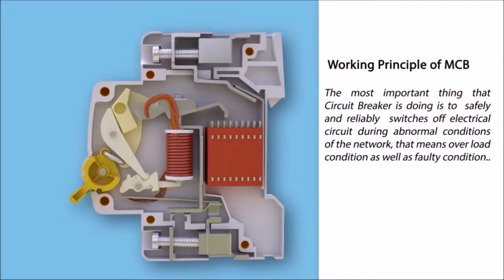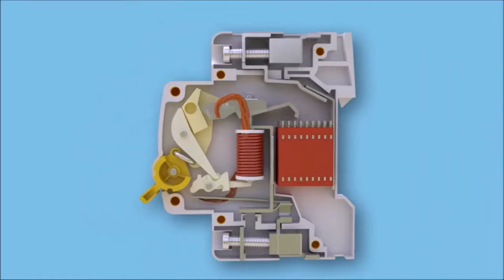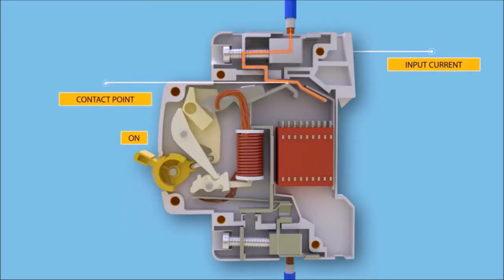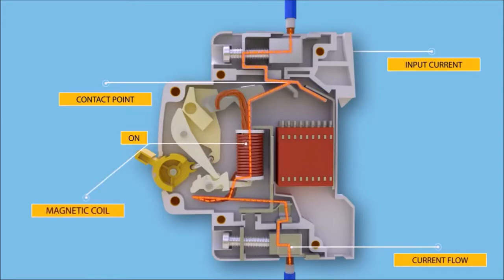Working principle of circuit breaker. The most important thing that a circuit breaker does is to safely and reliably switch off an electrical circuit during abnormal conditions of the network, that means overload condition as well as faulty condition. Under normal working conditions, the circuit breaker works when we switch the operator manually from position off to position on. Electric current carrying path shown in animation: first incoming terminal, then contact point of moving and fixed contacts, then magnetic coil, then bimetallic strip, then outgoing terminal. All are arranged in series.